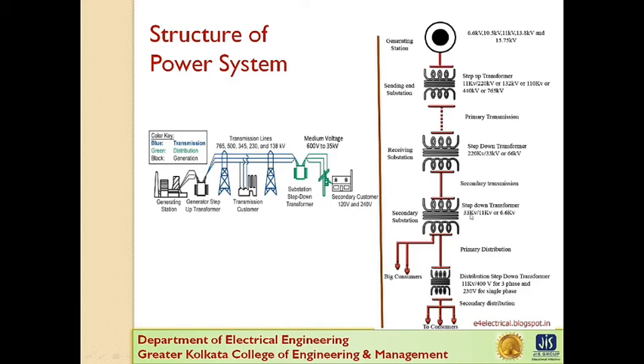The 11 kV lines run along the important roadsides of the city. This forms the primary distribution. Now, it may be noted that big consumers having a demand of 50 kilowatt are generally supplied at 11 kV for further handling with their own substation.